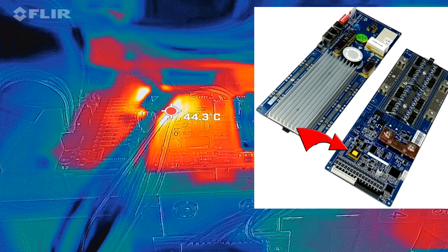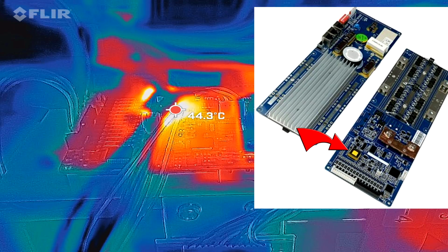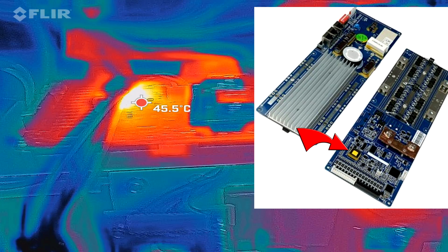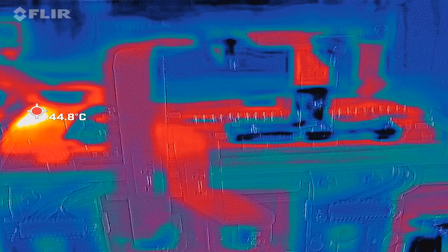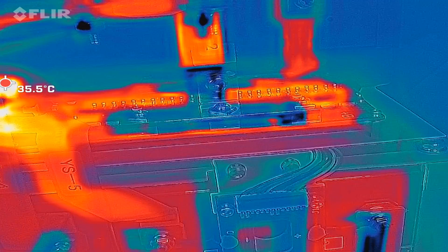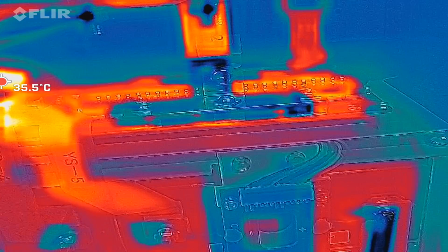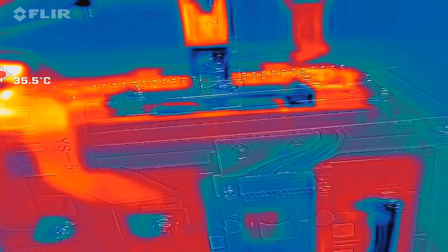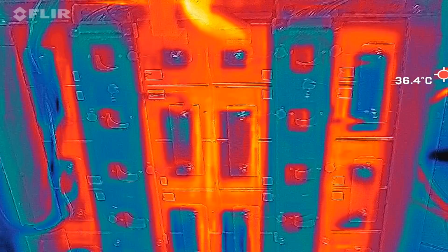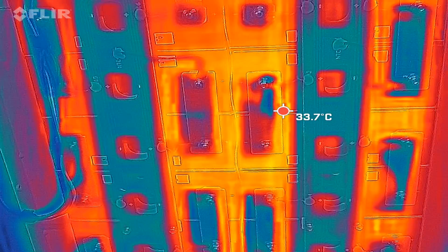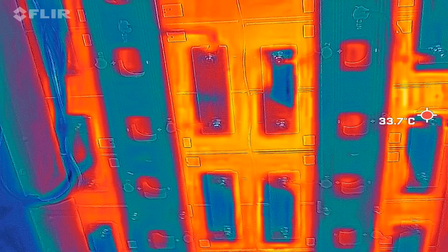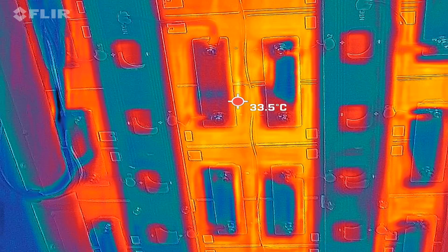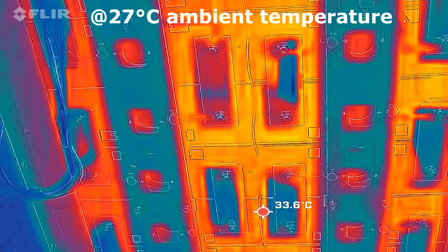See you then. So we still have this little transformer there with 45 degrees or something. Nothing unusual on this BMS. Let's have a look at all the bus bars. I've got like 35 degrees on the bus bar. And here the battery as such, what's the maximum temperature here? What are we talking about? 33, 35 degrees. 33 degrees.